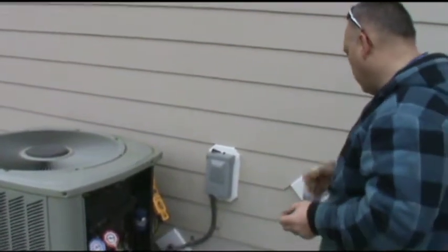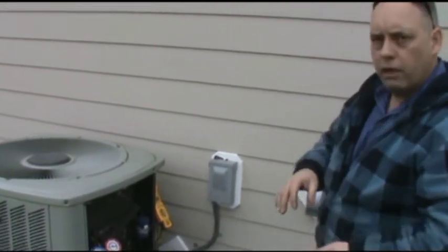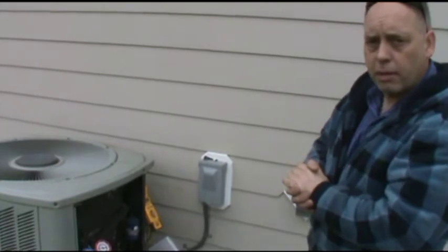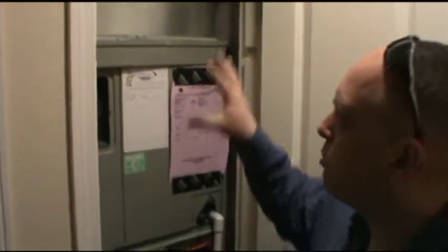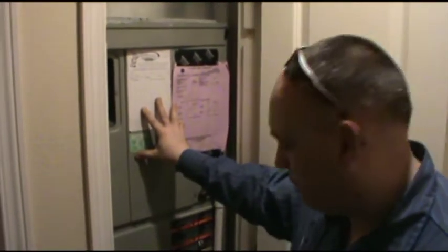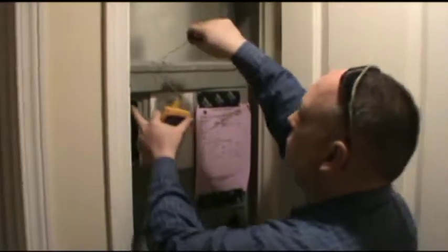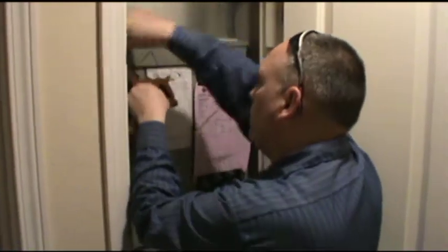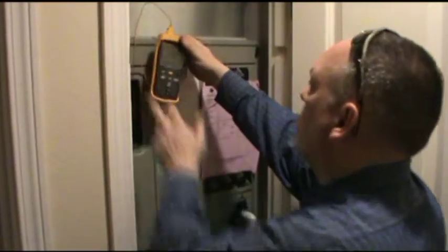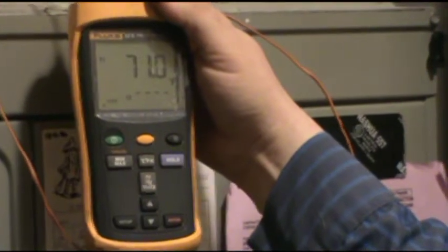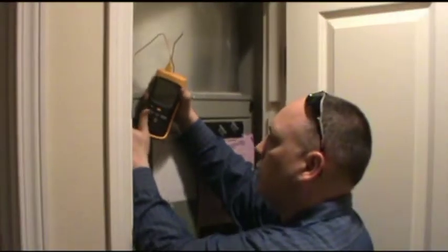And the last check that we need to do to evaluate how well this heat pump is running is we're going to go inside and take some temperatures. So now what we want to do is measure the temperature difference between the air coming into the air handler and the air coming out. The best way to do this is to stick my temperature probe into the return and get a reading. We have 70.9, which is roughly 71 degrees. And then we're going to go to the closest vent to this furnace and take a temperature reading there, which is right here in the bathroom, about 5-6 feet away.